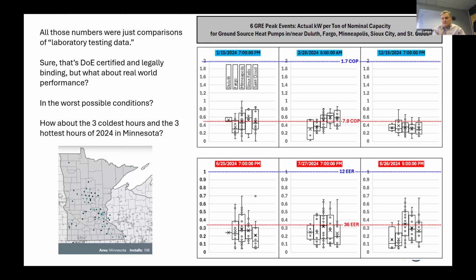So these are 3-ton units, 4-ton, 5-ton units. And the number you see on the left in the first graph, for instance, the red line goes through at about 0.5 kilowatts per ton of capacity. None of these units in the wintertime readings in Minnesota used any electric strip heat backup. That's pure heat pump operation. And of course, the same is true in the summertime, where you see EER really in excess of 36 for those 100 and something units that we measured. You can see on the left the map demonstration of where those units were located. And those are actual performances of each one of those units.